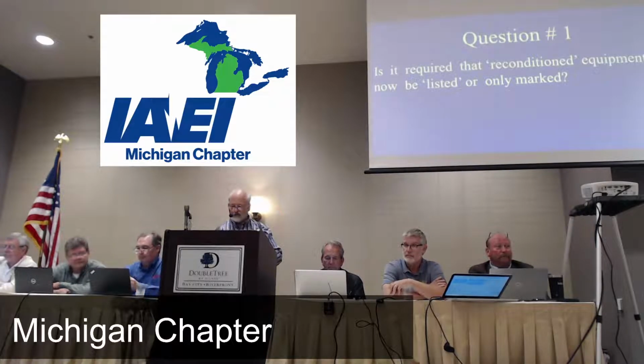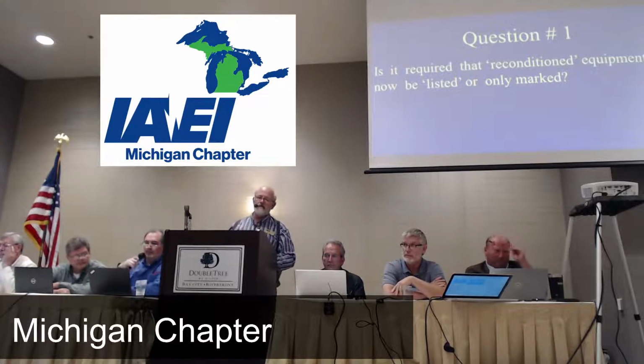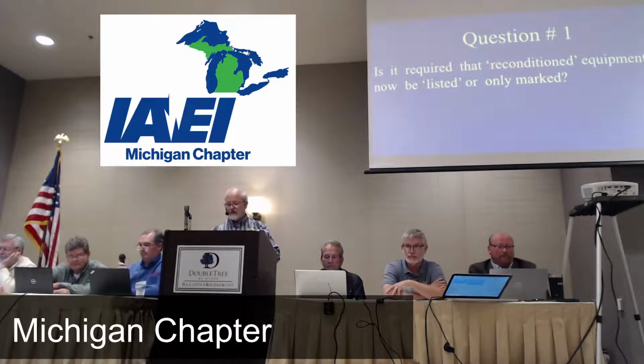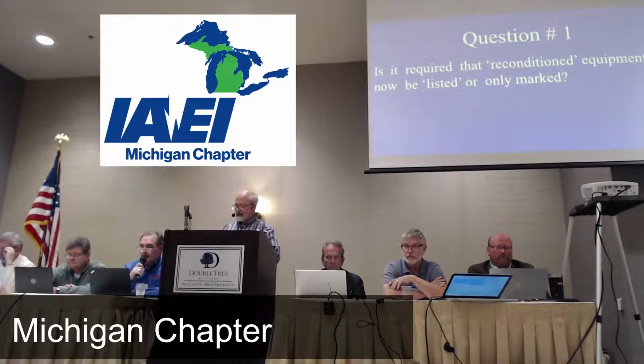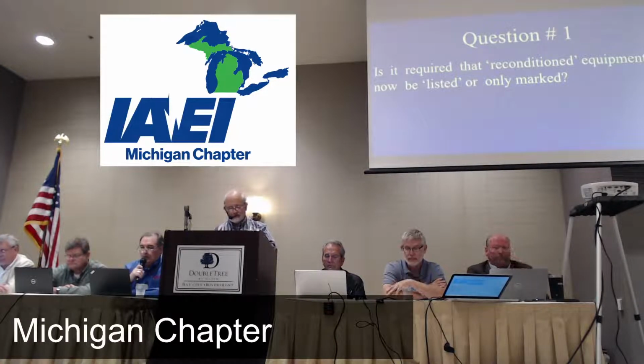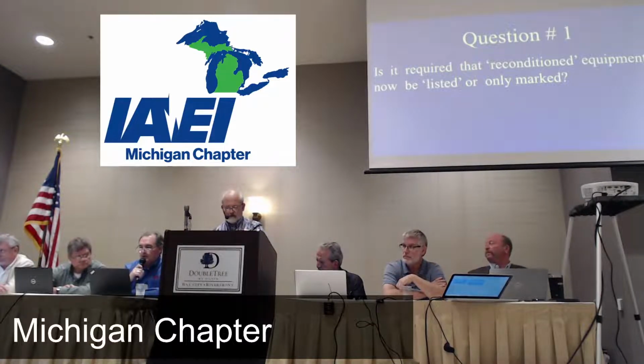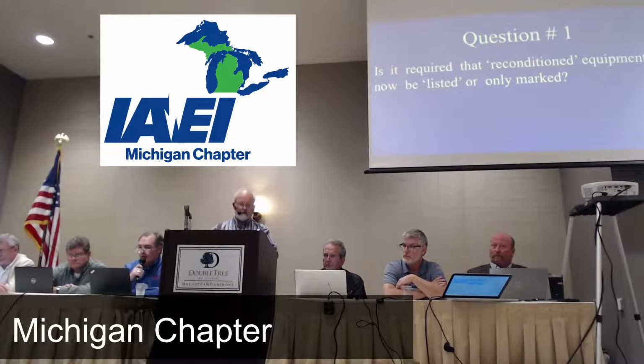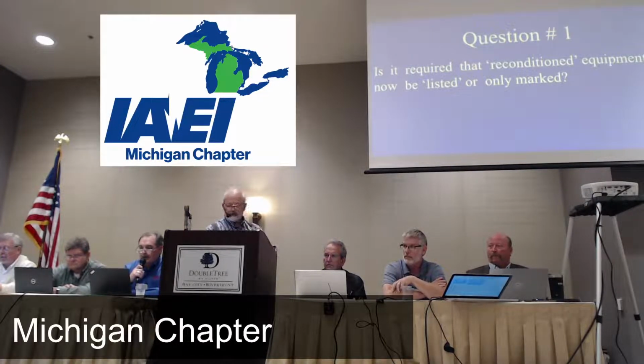First question goes to Tom. Is it required that reconditioned equipment now be listed or only marked? The answer is, in the 2020 NEC, each code-making panel was charged to review the equipment in their respective articles and determine if the equipment under their purview could be reconditioned. In some articles, they identified equipment that could not be reconditioned, such as molded case circuit breakers. And in other sections of the code, they required reconditioned equipment to be listed as reconditioned or field evaluated, such as switchboards and switchgear, in section 408.8.